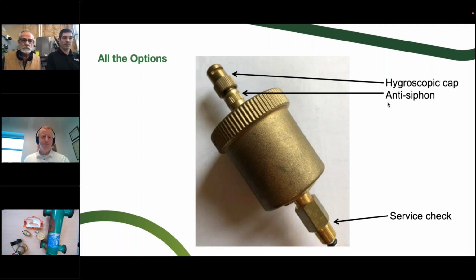For sure. And then we'll come back to the anti-siphon cap. We've got a graphic to show why that's important, but you want the air separator to be purging air. You don't want it to introduce air into the system. And there are some piping things and expansion tank location things that could happen that would allow air to come back in through an air vent.